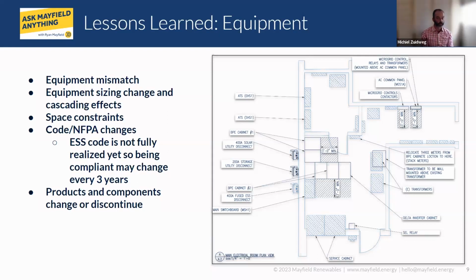Exactly. There's a 600 kilowatt hour limit, and we were within that limit at first, but then as the capacity of the batteries increased, the combined battery containers were greater than 600. So we had to separate them out by 10 feet, which means underground conduit, and maybe your maintenance pad is going to be larger, or maybe it doesn't fit in the same location anymore.